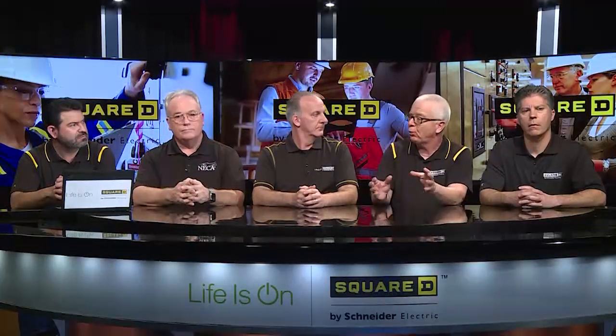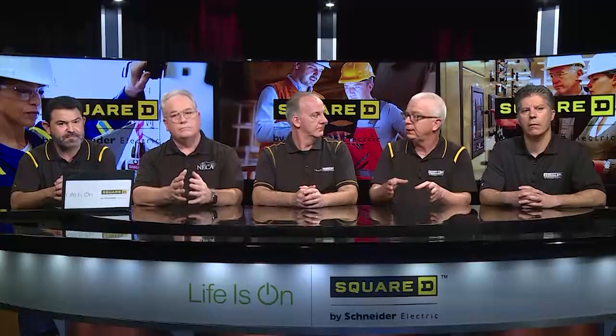That's really important from the listing agency and manufacturer's perspective, because I've got a piece of equipment that was built to a given product standard when it was brand new. If it leaves a facility, isn't in operating condition, and somebody reconditions it, the question is: does it meet the applicable requirements of that product standard after it was reconditioned? That's why we have to remove the listing mark and mark it with the name of the entity that did the reconditioning and the date, because now they're responsible for that piece of equipment.